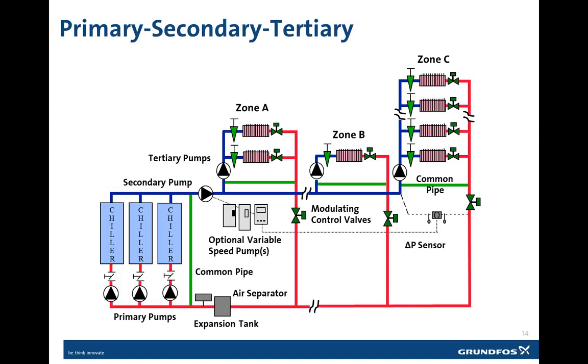Now, another type of design is a primary, secondary, tertiary design. And it has a few important variations in this type of design. As you can see here, we've added a third set of pumps as well as additional common pipes for each of the zones or buildings. Now, multiple secondary and tertiary pumps may be used. A single pump is just shown here due to the space allowed for this drawing, so it doesn't have quite all of the same controls that you'd normally see, again, based on the space for the design.